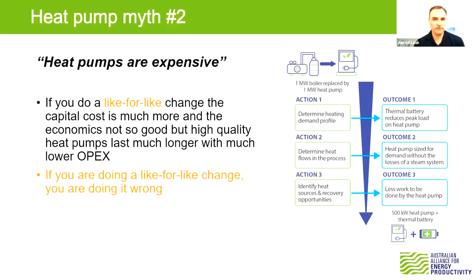To explain further: if you've got, say, a 1 megawatt steam boiler or 1 megawatt hot water generator, when replacing that with a heat pump, if you look at the reduced heat losses and size this correctly - whether with thermal storage, making it perform and take out the peaks using thermal storage - your heat pump should be a lot lower. In the example we've shown here, and we've seen this in various studies, a 1 megawatt boiler can regularly be replaced with a 500 kilowatt heat pump, say, with a thermal battery. So if you're doing it like-for-like, you're definitely doing it wrong, and it's definitely going to be expensive.